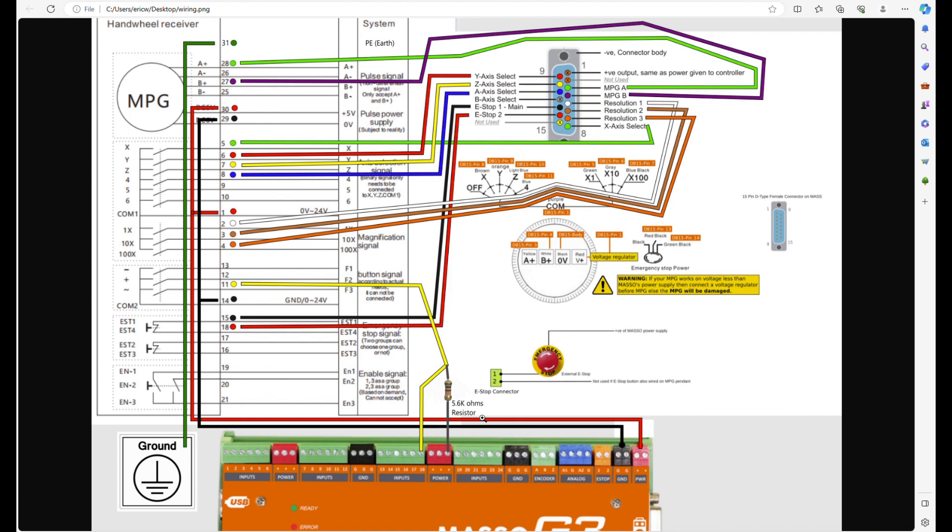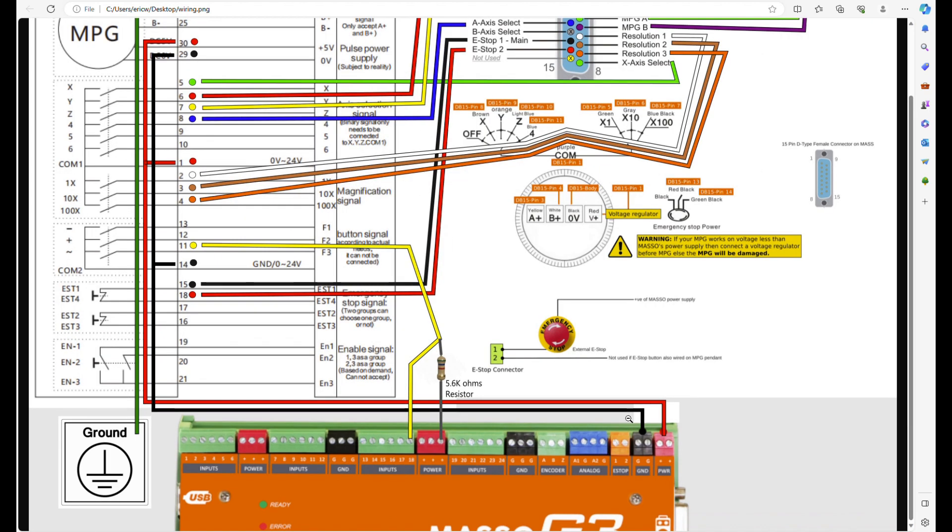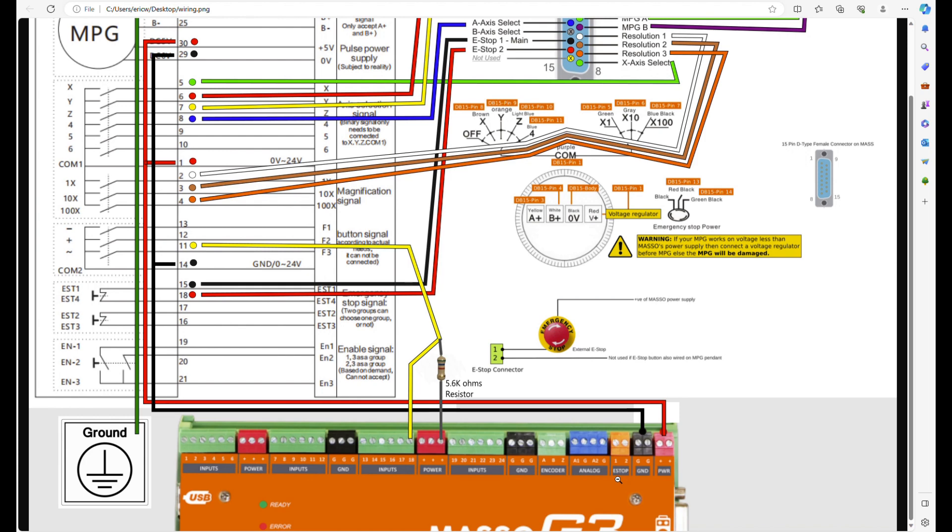The emergency stop, the way it comes from the factory, has a black and a green wire hooked up into EST2 right here. And you have to unhook the black and move it into EST1, but leave the green in EST2. With that configuration, both E-stops work. The one on the G3 touch, right on the front of the controller, and one on the pendant.